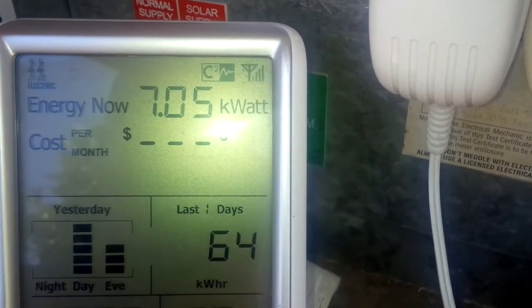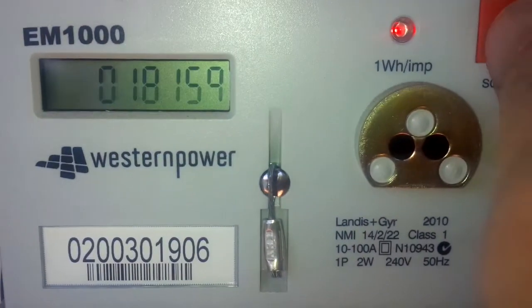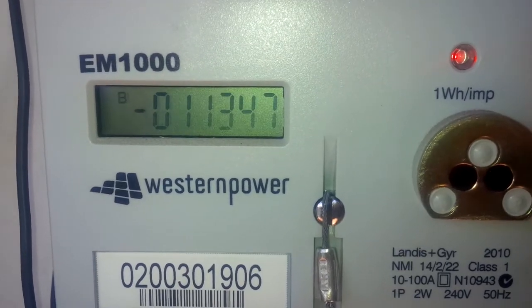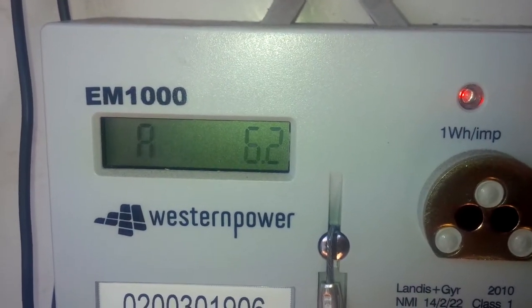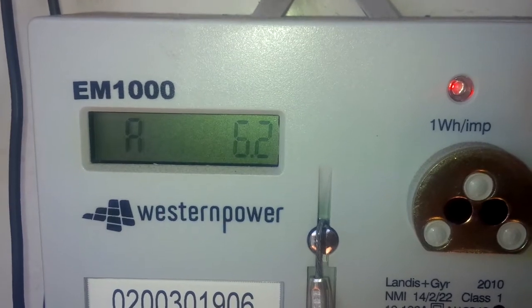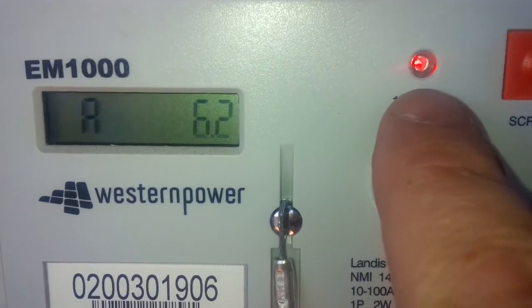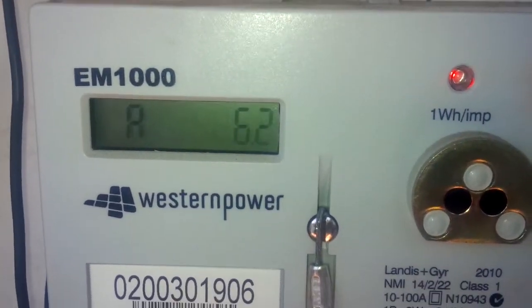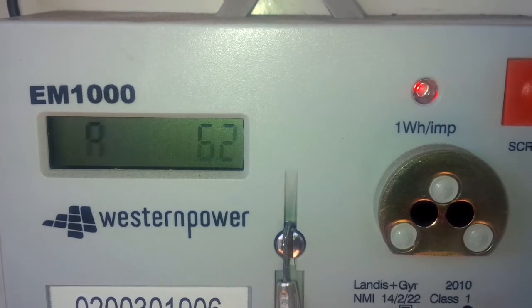Note that these numbers are pretty rough because of the way that they're measured. If I go across to the meter, you'll see that we have a current draw being registered from the grid as 6.2 amps, however the light is not flashing. This is because we're using some reactive power from the grid which we're not being billed for.